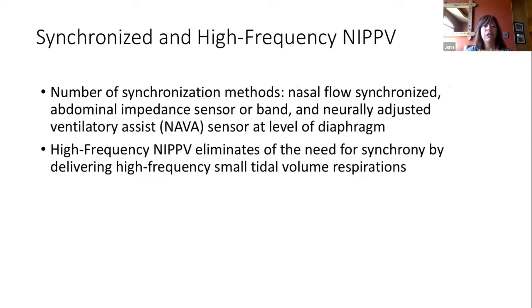So there are a number of methods in use to synchronize these high pressure breaths during NIPV, and that's either with a nasal flow modulator, an abdominal impedance sensor band, or neurally adjusted ventilator assist, or NAVA, which is a sensor at the level of the diaphragm. And this is something that is very new and gaining popularity in terms of its use. And then there's high frequency NIPPV. So you can actually use your oscillator or jet to produce very high rate, low tidal volume breaths. Essentially, because it's such a high rate and such small volumes, this eliminates the need for synchrony.